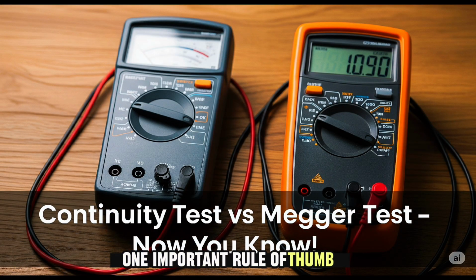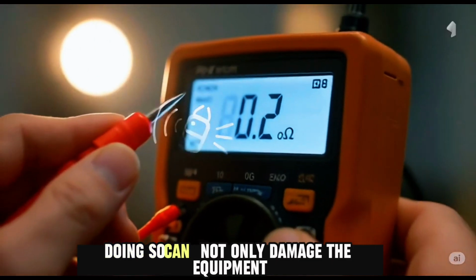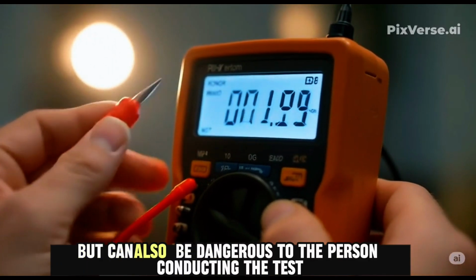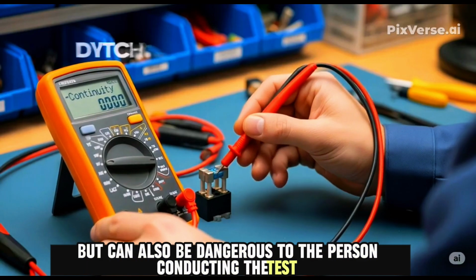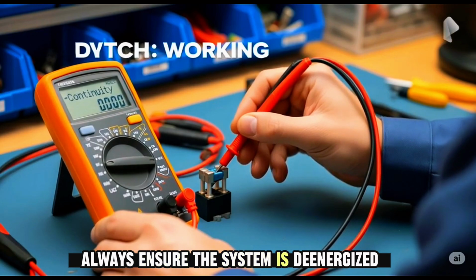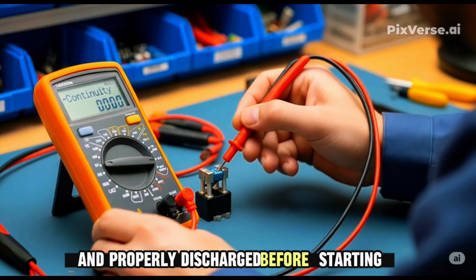One important rule of thumb: never perform a Megger test on live or energized equipment. Doing so can not only damage the equipment, but can also be dangerous to the person conducting the test. Always ensure the system is de-energized and properly discharged before starting.